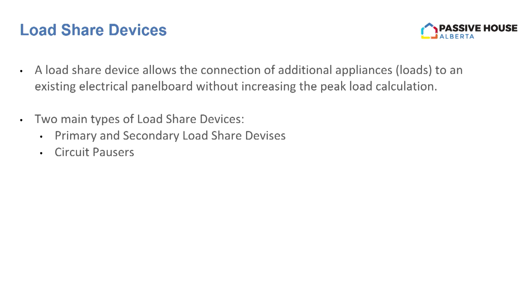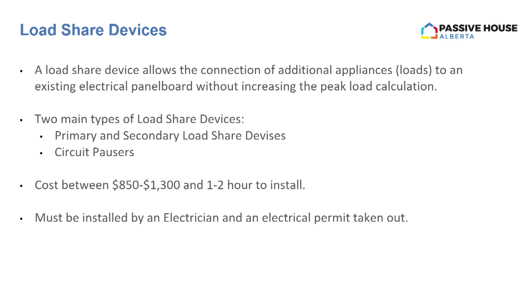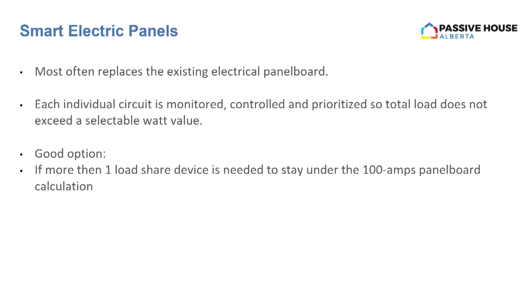And the nice thing is these things only cost like $850 to $1,300, and 1 or 2 hours to install them, so pretty low cost. You do need to use an electrician and you do need to take out a permit, but it's still pretty low cost. If after doing those load share devices you still don't quite make it onto 100 amp service, then you could use what's called a smart electrical panel, as maybe the prices come down and they become more prevalent. A smart electrical panel is basically a load share device on every single circuit. So every single circuit is controlled, monitored, prioritized, and then you can also do utility billing for it. So they're a good option if you need more than one load share device to stay on 100 amps.